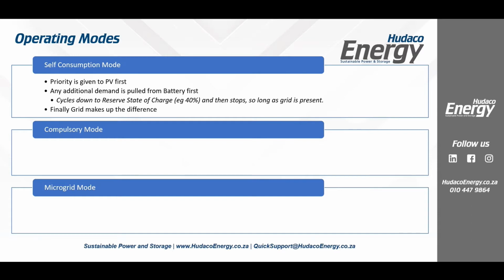Okay, that's self-consumption mode. Most of the systems that are installed are in that mode. Every so often, we also have compulsory mode. Compulsory mode is a manual override. Basically, the system does what you tell it. You can tell it to charge, discharge, or stop. We're talking about the battery operating modes at this point.